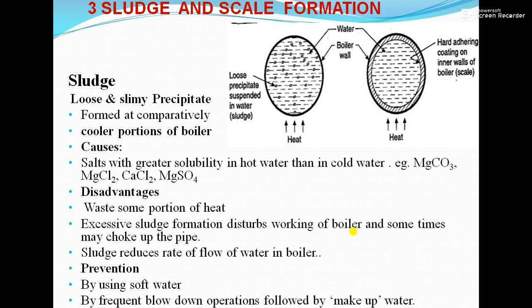So what is sludge and what is scale? You can see the diagram and distinguish between scale and sludge. Sludge is the loose and slimy precipitate present in the water, present in the cooler portion of the boiler. Scale is the hard, adherent coating present on the surface of the boiler metal, in the hotter portion of the boiler.